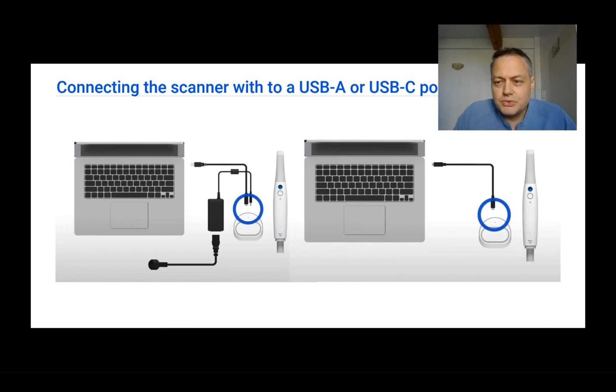If you are using a USB-C cable, it provides the needed power for the scanners to work properly. The minor disadvantage is that USB-C sometimes charges a little slower than a socket connection, so warm-up may take slightly longer. However, it's a simpler connection and avoids extra cables. Note that USB-C can be USB-C 3.2 or USB-C Thunderbolt — Thunderbolt operates at higher speed, so if available, connect to the Thunderbolt port.